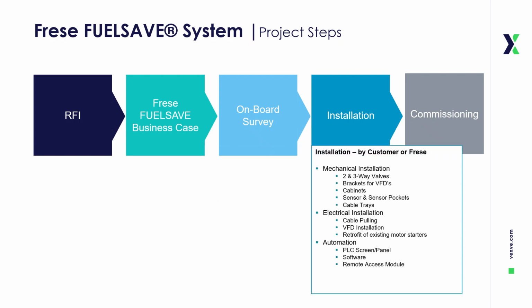Step 4 is installation, which can be carried out either by the customer or by Frese. The mechanical installation includes fitting 2- and 3-way valves, brackets for variable frequency drives, cabinets, sensors, sensor pockets, and cable trays. On the electrical side, the process involves cable pulling, installation of VFDs, and retrofitting of existing motor starters. Automation is also integrated with a PLC, a control screen or panel, and the necessary software. In addition, a remote access module is installed to allow secure monitoring and support. This stage brings together all mechanical and electrical elements, ensuring that the FuelSave system is fully and reliably integrated into the vessel's operations.